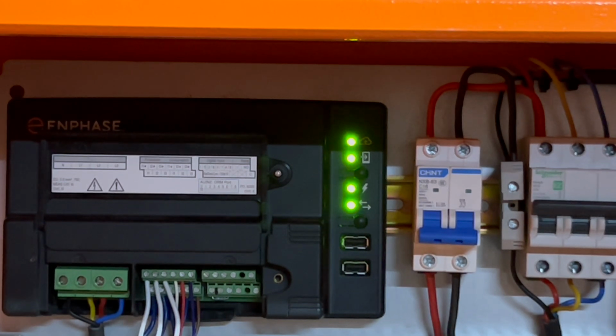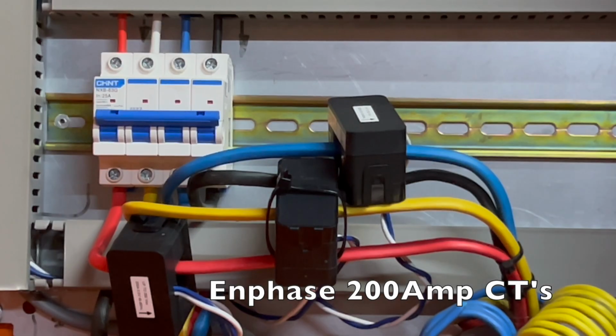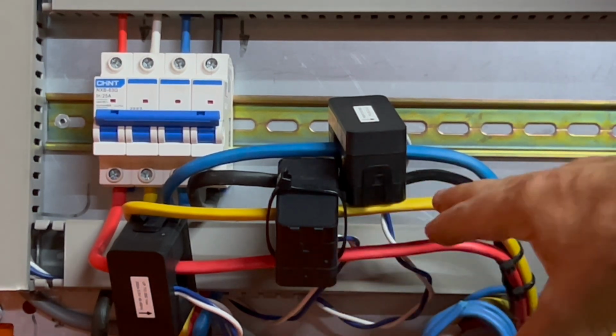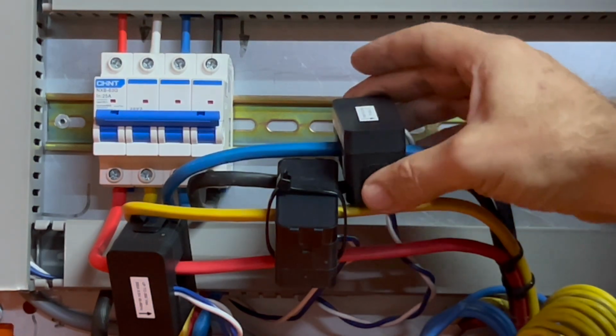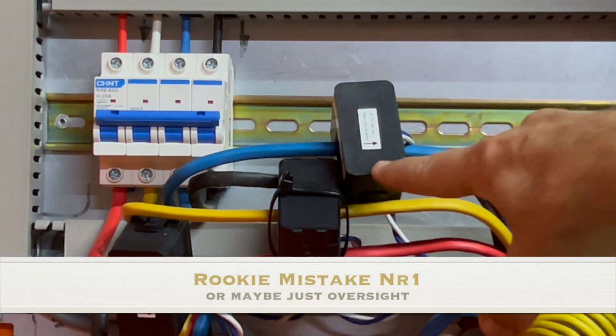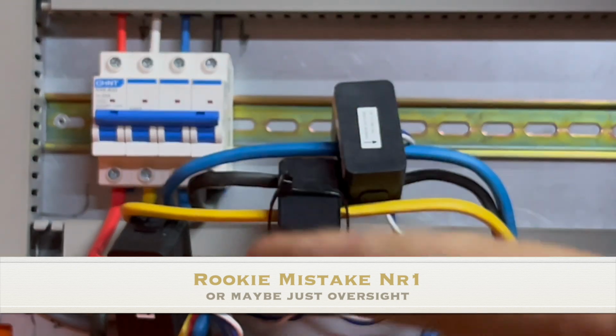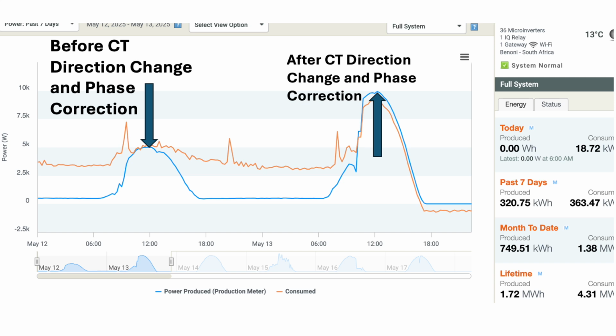And this particular site phase sequence is in reverse, so we had to swap out the red and yellow because the red and yellow is swapped throughout the entire site. Other issue we had was on the CTs. The CTs are obviously directional, and you can see the little arrow over there. So the CTs were pointing in the wrong direction. What that did on the monitoring of the system was it actually halved all the production from the micro inverters.